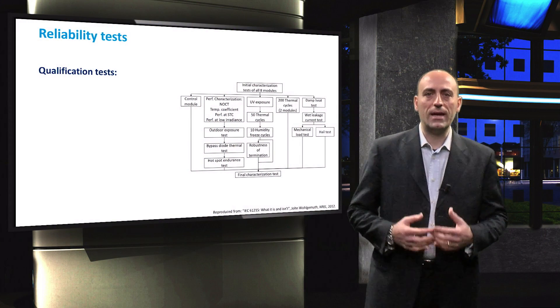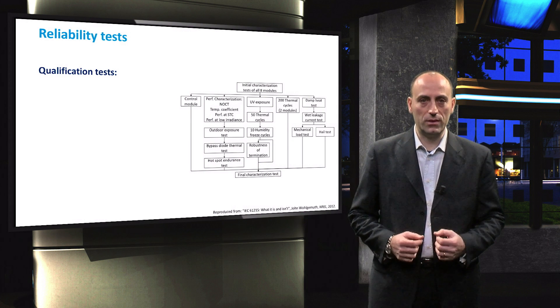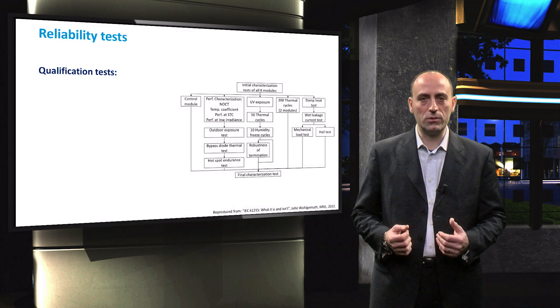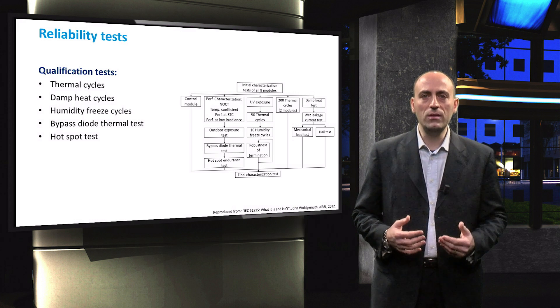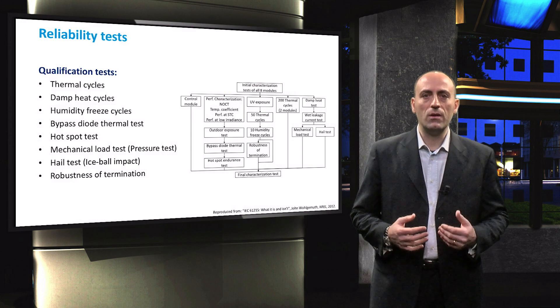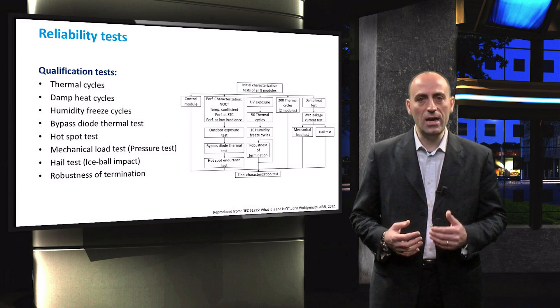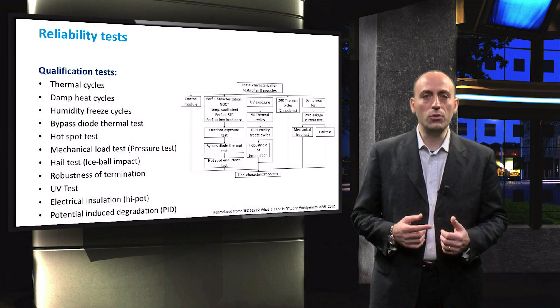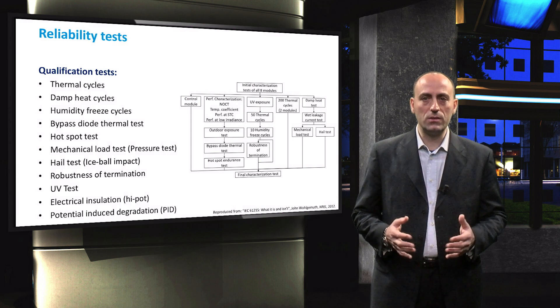Nor does it seek to discern the root cause of performance loss. Here we list a number of reliability tests, most of which are also prescribed by the IEC 61215 standard. The failure modes to be tested can be divided into climate, mechanical, radiation, and electrical failures. More specifically, there are multiple climate tests such as thermal, damp heat, and humidity-freeze cycle tests. Next, there are the mechanical tests such as mechanical load tests, the so-called pressure tests, and the hail tests, also called the ice ball impact test. Other tests are, for example, UV, electrical insulation, and the potential induced degradation tests.